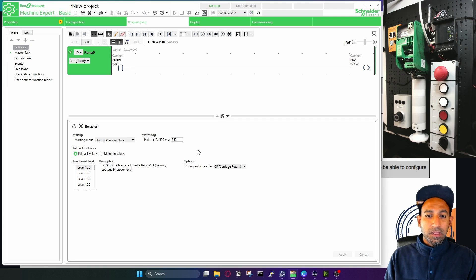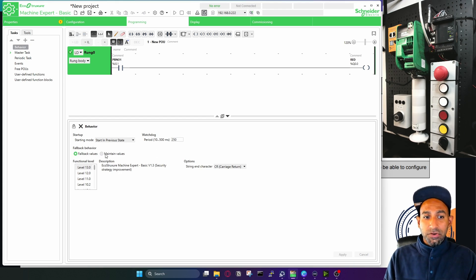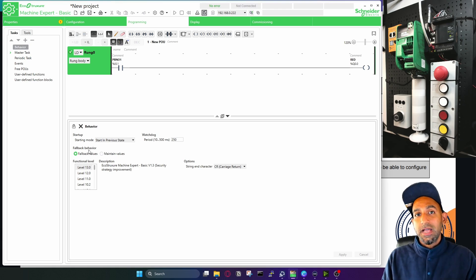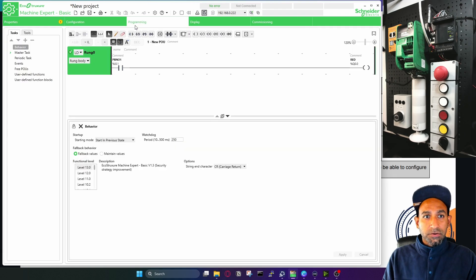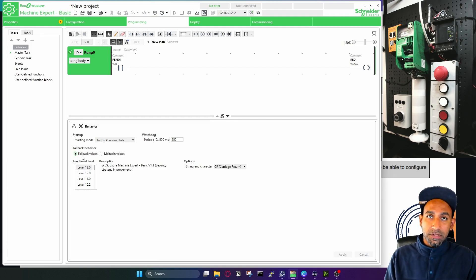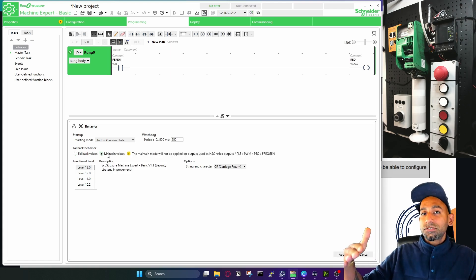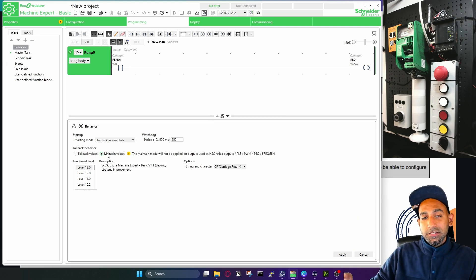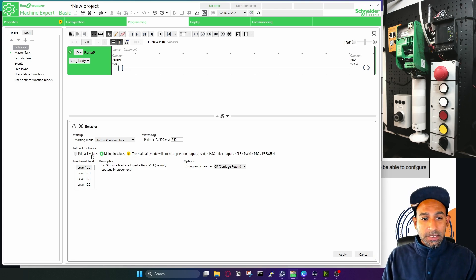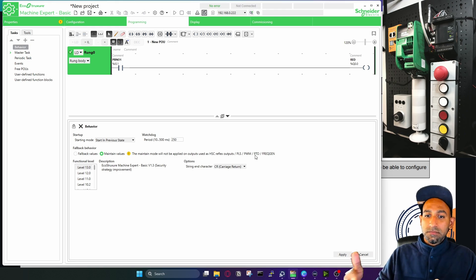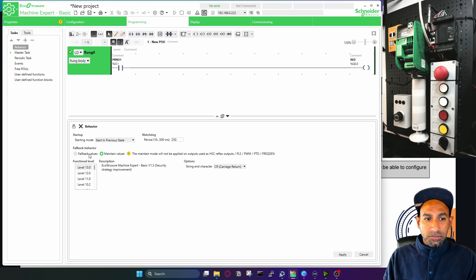Then you have fallback behavior — what happens if the PLC goes into error mode? You can have fallback values or maintain values. Fallback values are related to outputs: if the PLC goes into a fatal or error state, the output will go to the fallback values (all false, as declared in configuration). If you choose maintain values, and the output was true when the PLC errored, it will maintain that true signal. I prefer to keep it on fallback values.